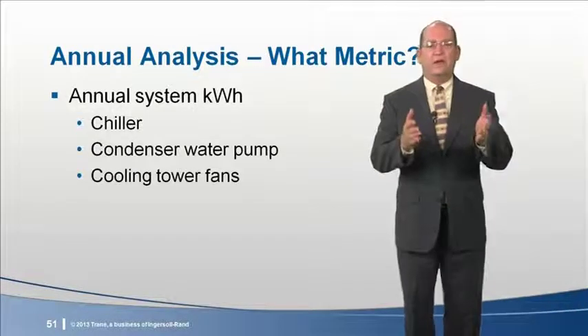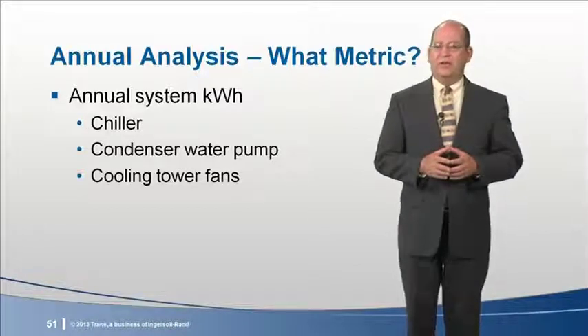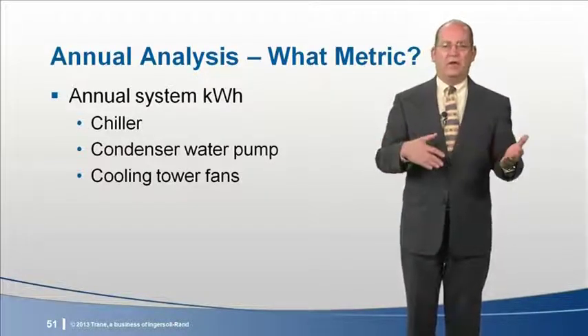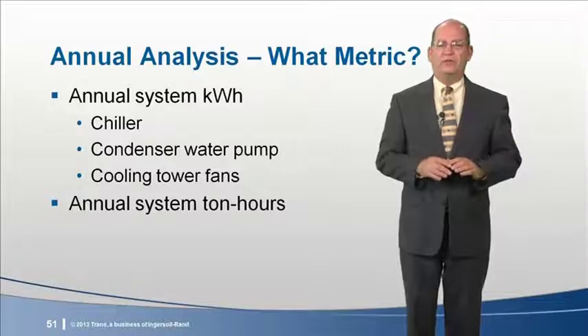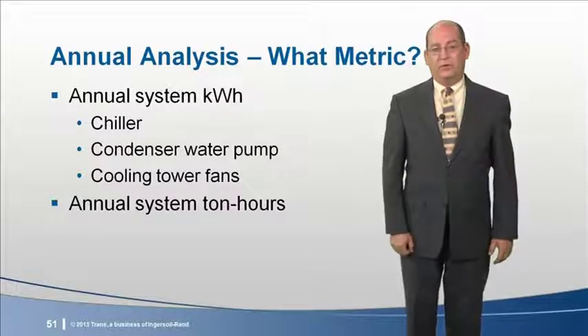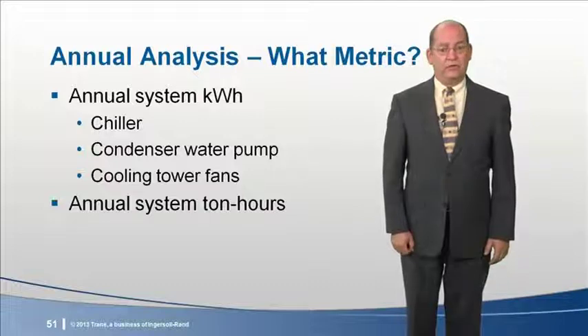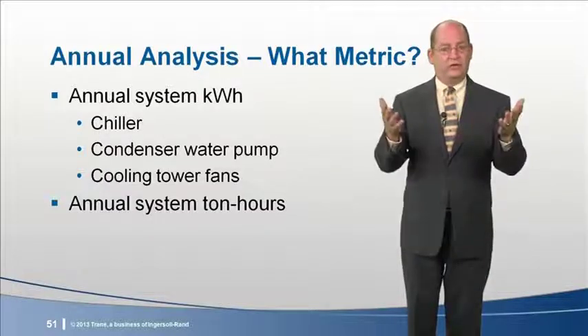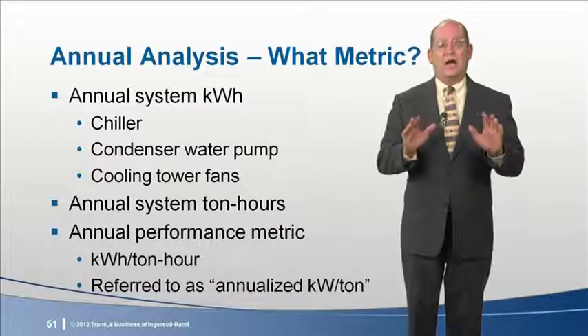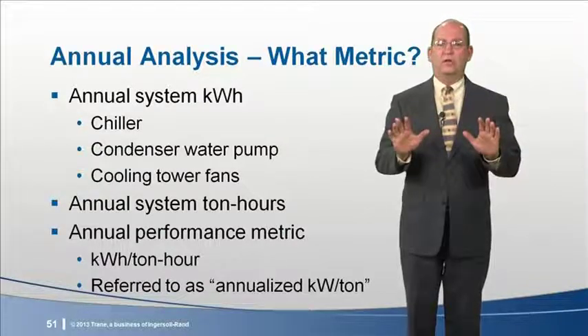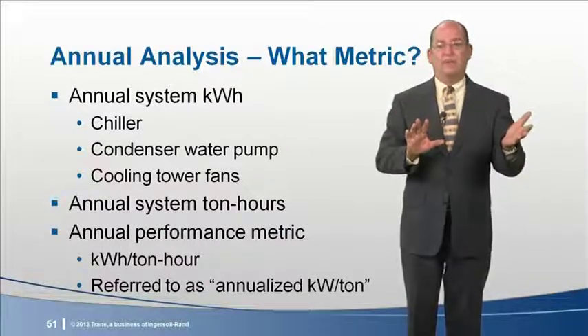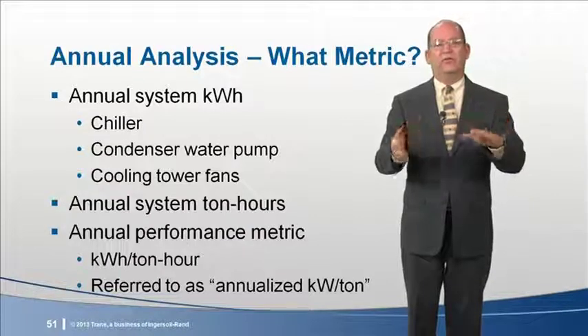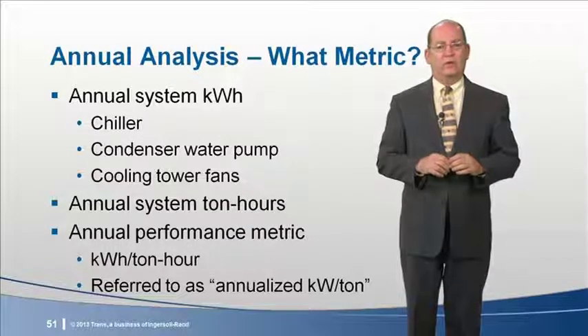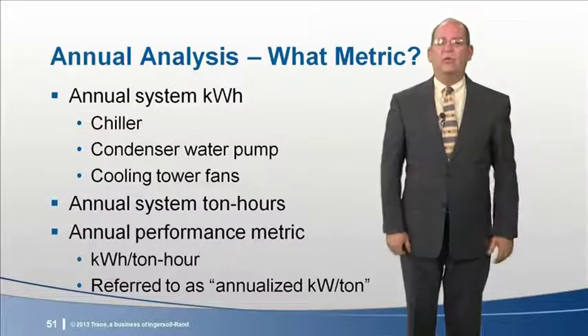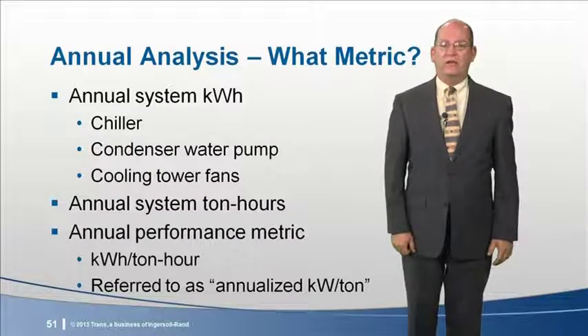For our analysis, we'll calculate the annual energy usage in the system in terms of kilowatt hours. We'll also calculate the annual system ton hours. For example, a chiller operating at 300 tons for 2 hours must provide 600 ton hours. Our annual performance metric today will be kilowatt hour per ton hour. That is the annual system kilowatt hours divided by the annual system ton hours. By canceling the hours, we'll shorten the term to annualized kW per ton for the chilled water system.